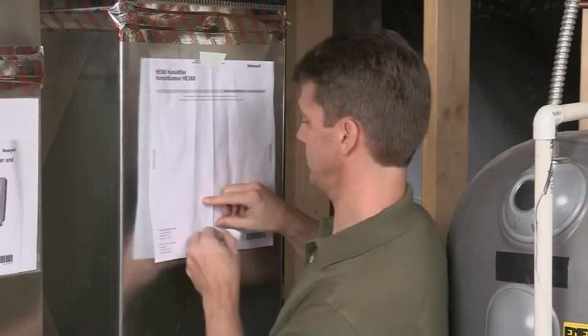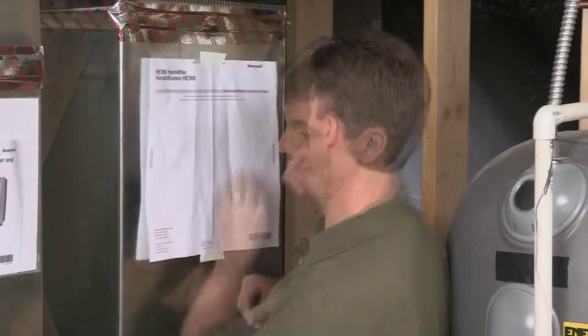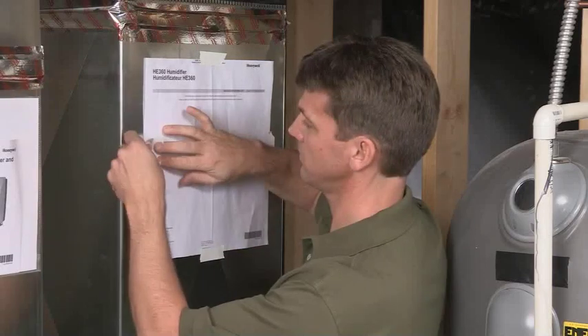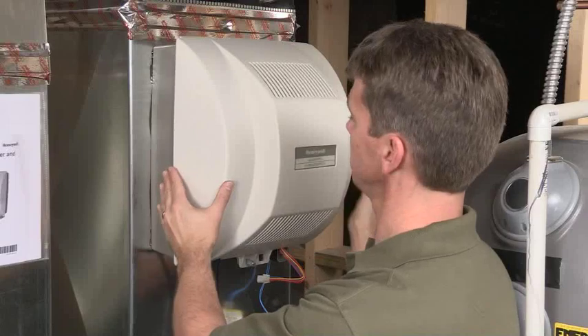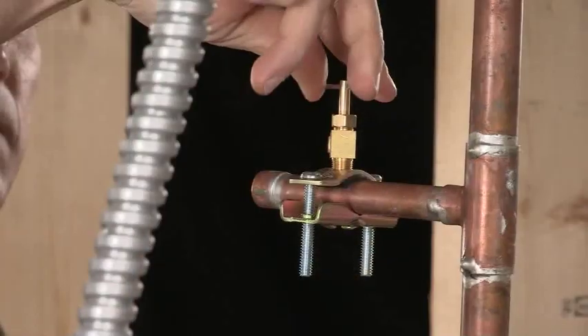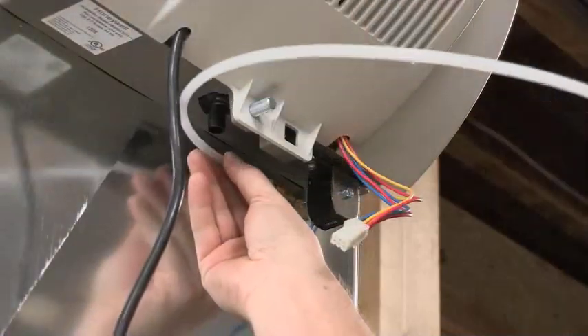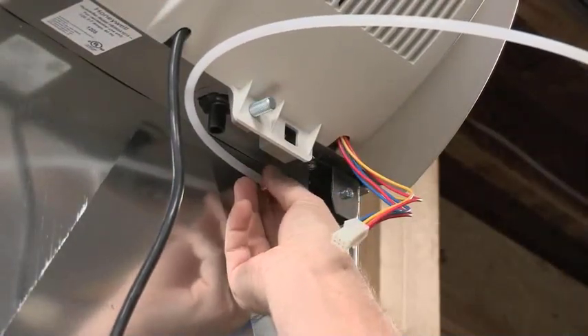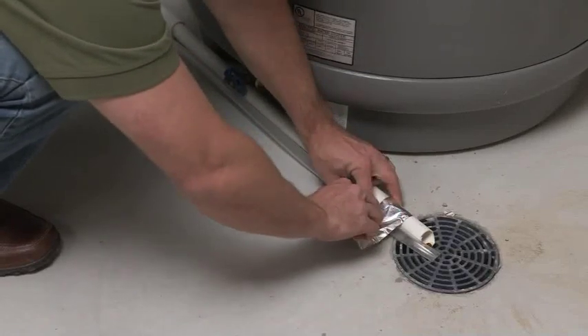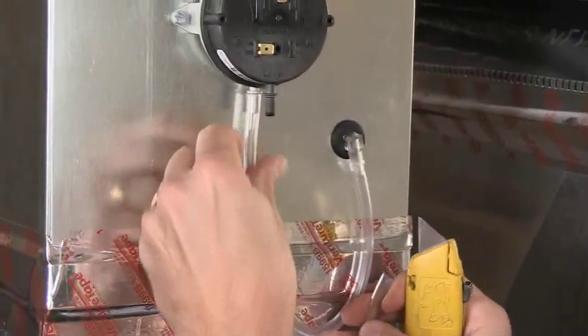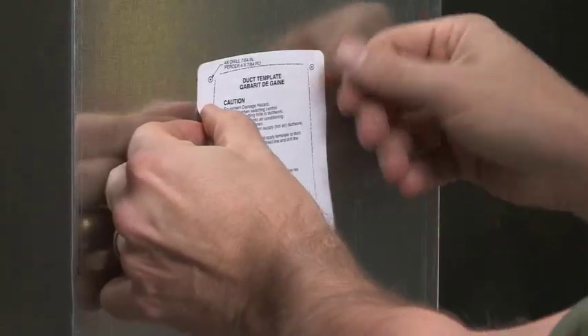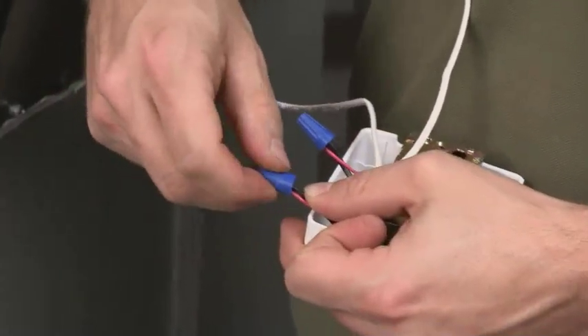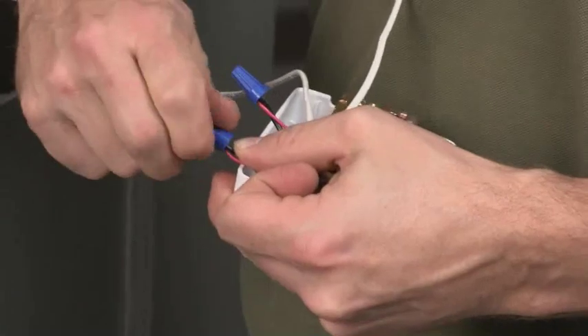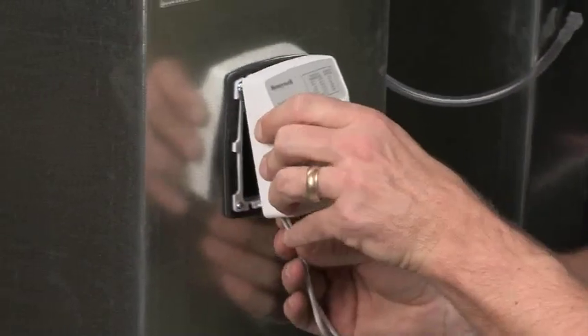After selecting the proper location for your humidifier and related accessories, the templates show you how to cut the openings for them in the ductwork. Once the humidifier housing is in place, you simply tap into the water supply, connect it to your humidifier, and run the drain tube to the floor drain. You then connect the pressure switch and tubing to the ductwork. Templates again help you install the switch and the humidistat. Finally, wire the system together using the diagrams provided and begin enjoying the comforts of humidified air in your home.